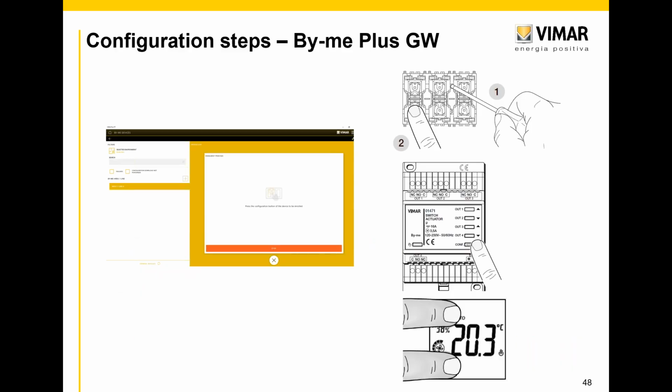This has to be done locally on site. So until now you must be on site. You have to enroll the devices, pressing the configuration button, and then place a name. Really pay attention to the naming even here on the devices, because you have to indicate in which room, for instance, the push button is. Otherwise, if you have many push buttons and you don't choose the right environment, later on it will be quite complicated to recognize which button you want to use.